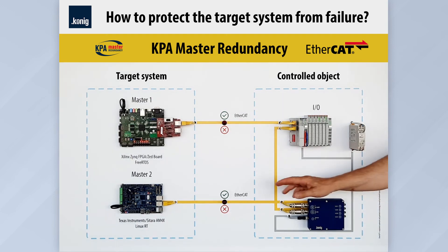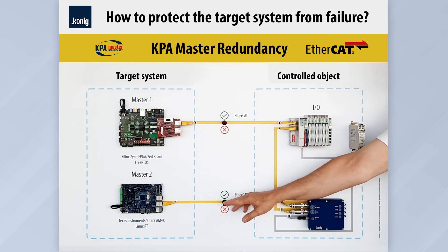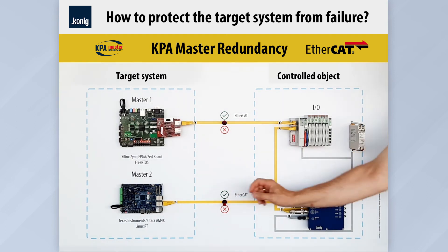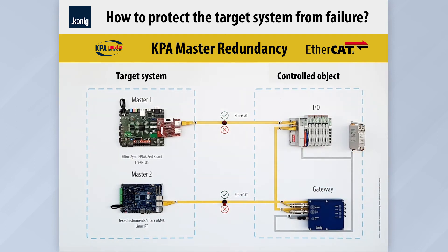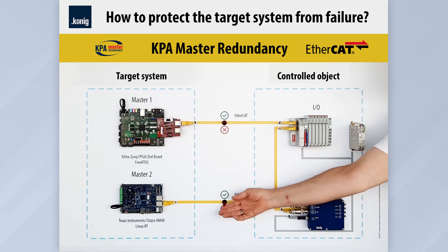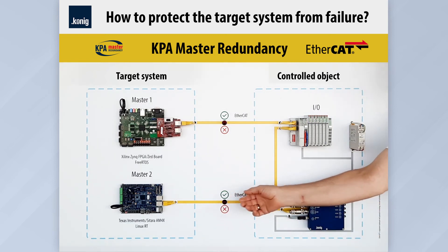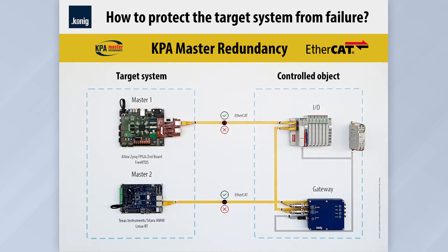Using the bottom switch, we simulate an operating failure of the currently active master, causing the upper master to take control again and become the leader. When the switch is turned back on, the lower device is connected to the network and goes into passive mode.